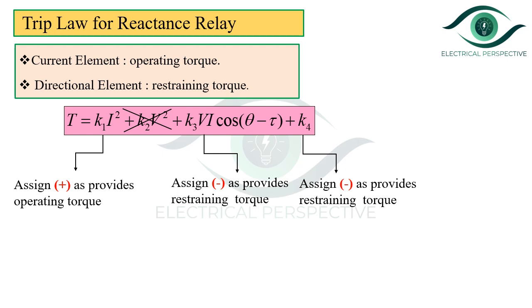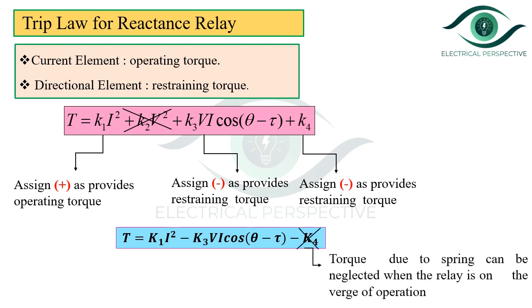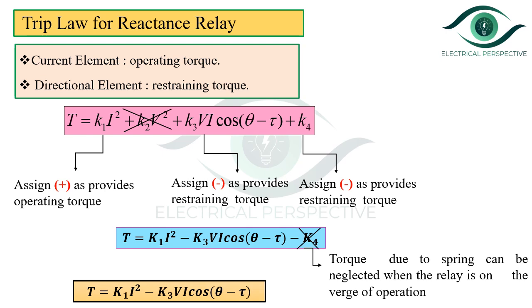We also assign a negative sign to K4 because it provides restraining torque — it is the restraining torque provided by the spring. Thus we get T = K1·I² − K3·VI·cos(θ − τ) − K4. Neglecting the spring torque when the relay is on the verge of operation, we get T = K1·I² − K3·VI·cos(θ − τ).